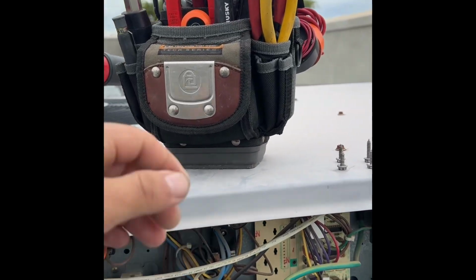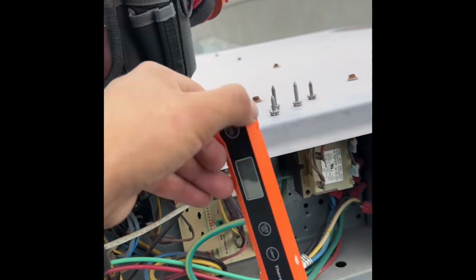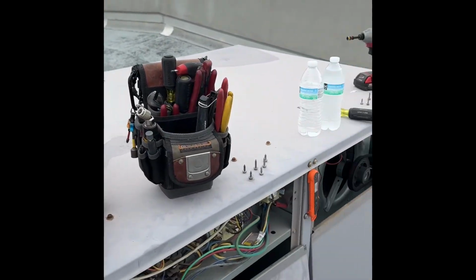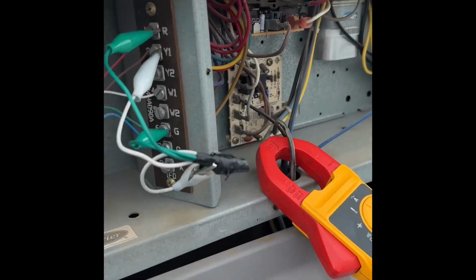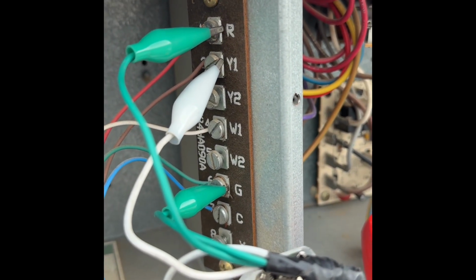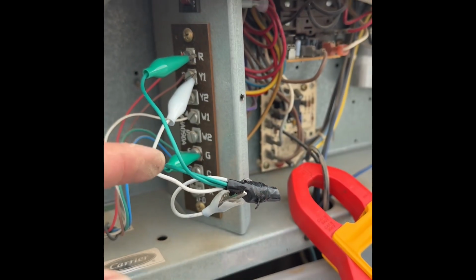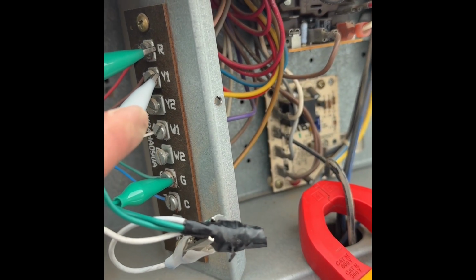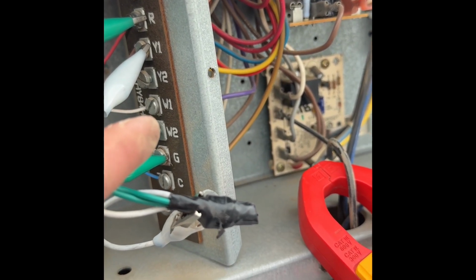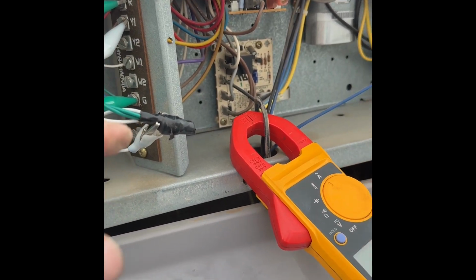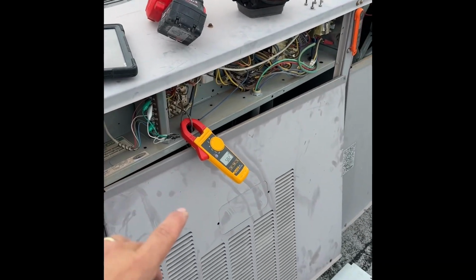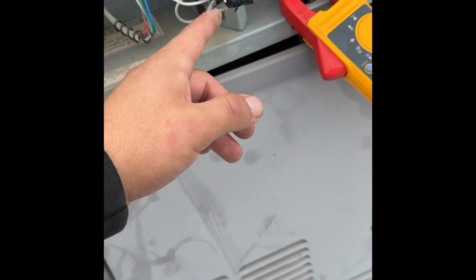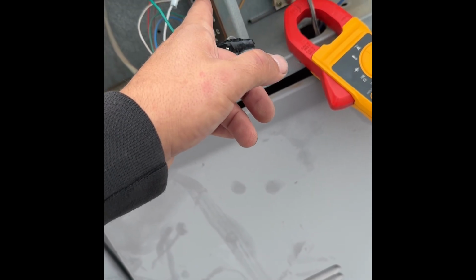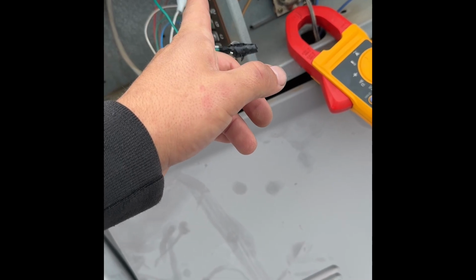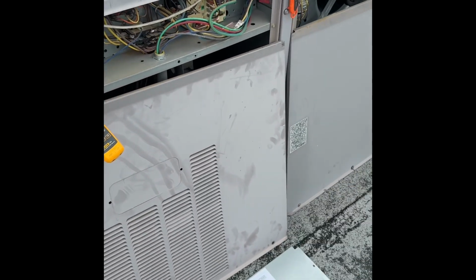I'm gonna bust out my tools and walk you guys through the second step after you get the unit running. All right, so as you can see, we got the fan spinning, blower spinning. Here's a visual for you guys to understand if you didn't get it verbally on how to set up your jumpers. You're also going to test it in heating too, which is the white wire, W1 terminal, which stands from there to there. Or because this is a heat pump, depending on how the reverse valve is set up, we might use the extra jumper to W and leave the white one on Y1.